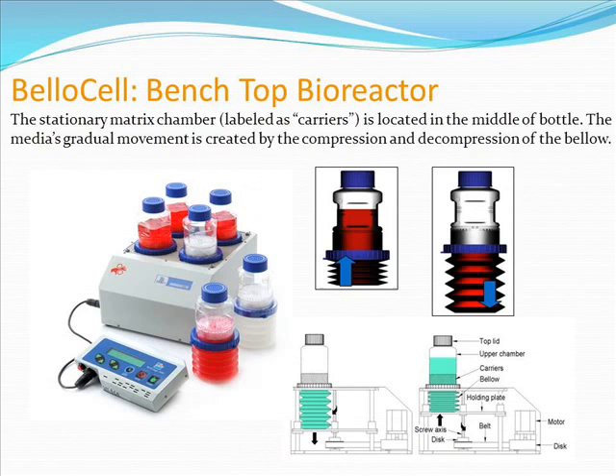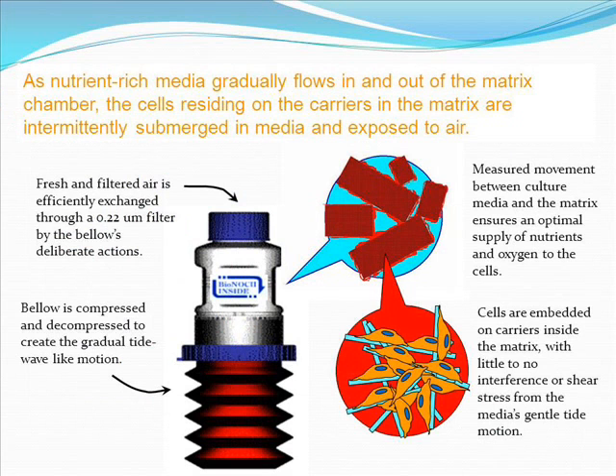In our benchtop bottle system, the BelloCell, the stationary matrix chamber is located in the middle of the BelloCell bottle containing a high density of cells attached to carriers. The compression and decompression of the bellow beneath this matrix chamber adapts the roller bottle principle with its gradual motion. The gradual motion of media allows for optimal oxygen and nutrient transfer into the cells residing on the carriers inside of the stationary matrix. The measured movements of the bellow draw air through the top filter and alternately submerge the cells in nutrient-rich media.